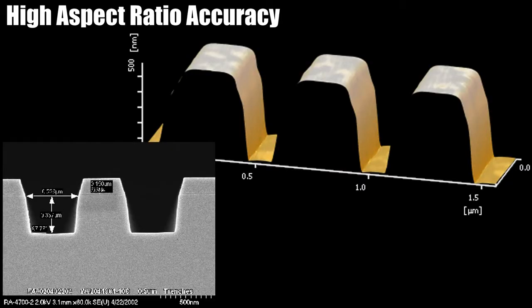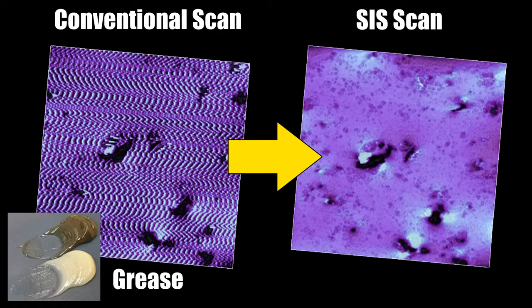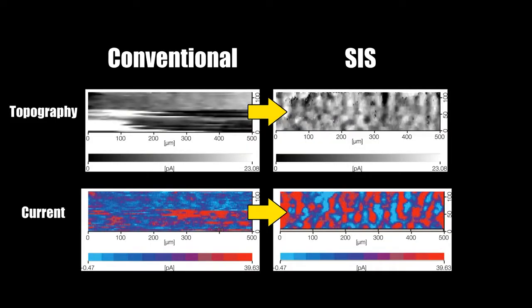Exactly. So besides sticky or soft samples, what else would this be good for? SIS mode also works gangbusters on high aspect ratio samples. A normal contact mode scan has a real hard time measuring steep slopes. SIS mode allows more accurate AFM metrology for critical dimension measurements. So just in these few examples, I can see a huge difference this makes in the data I'm now able to collect from samples I thought were a total write-off. Not just are you able to measure these difficult samples, but you're able to do it simply, more repeatably, and with higher resolution than you could do it before.